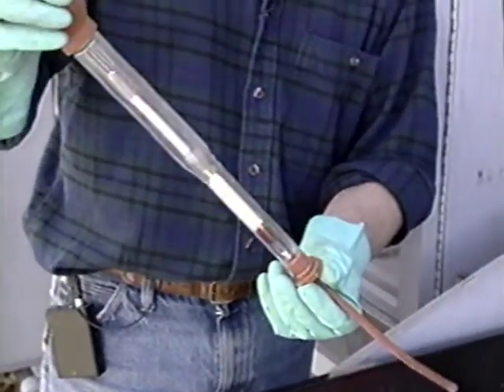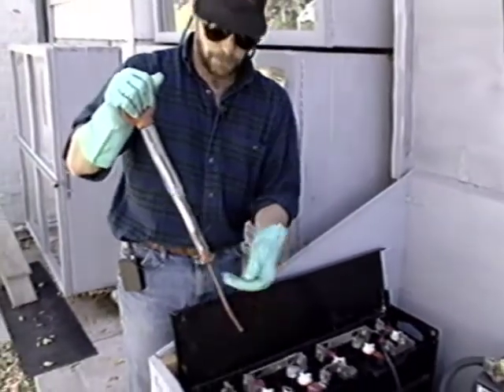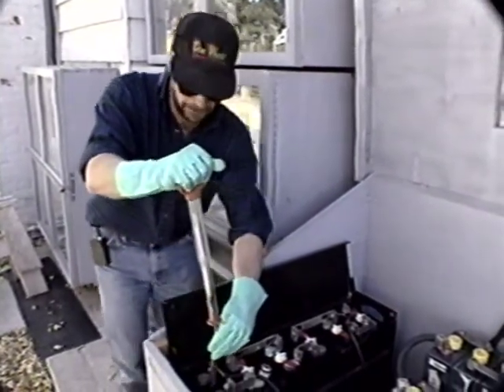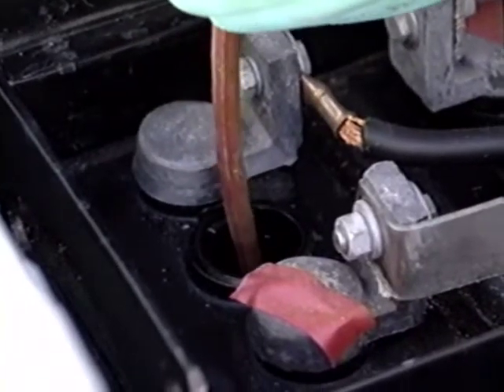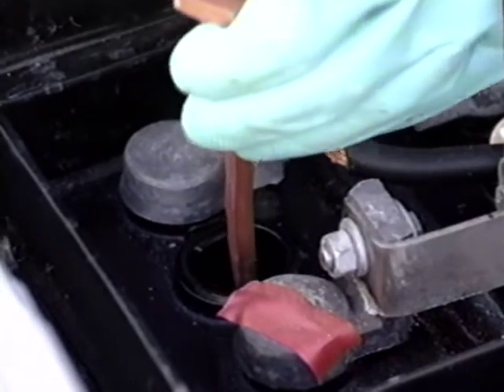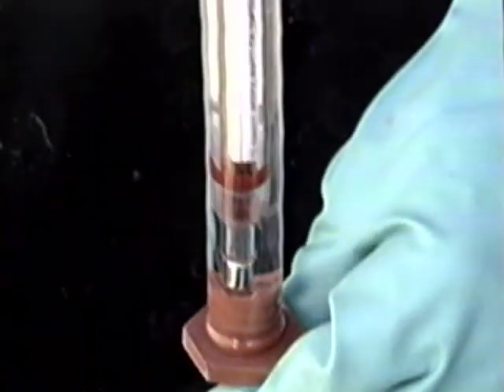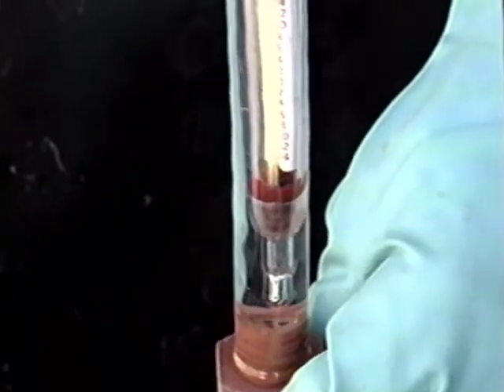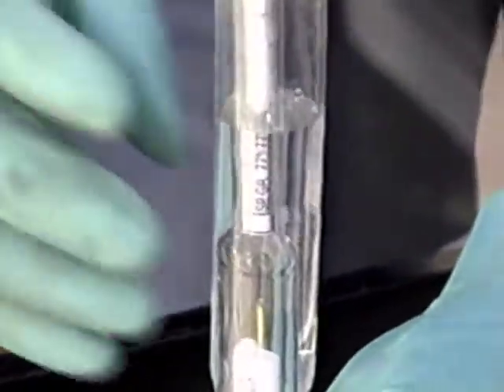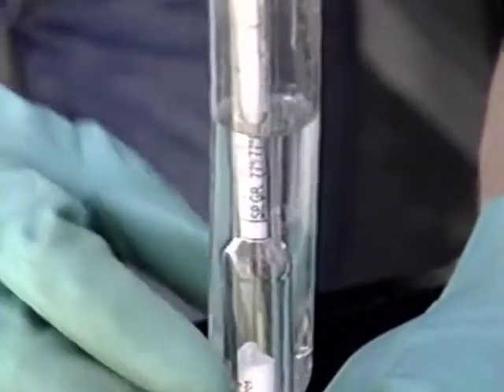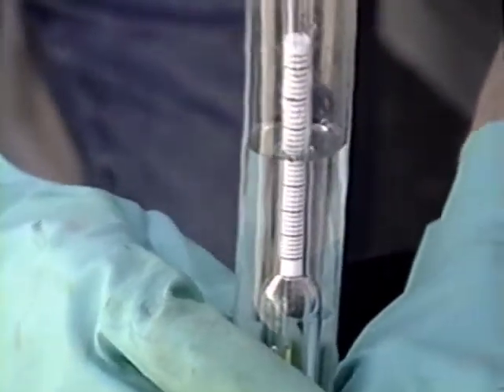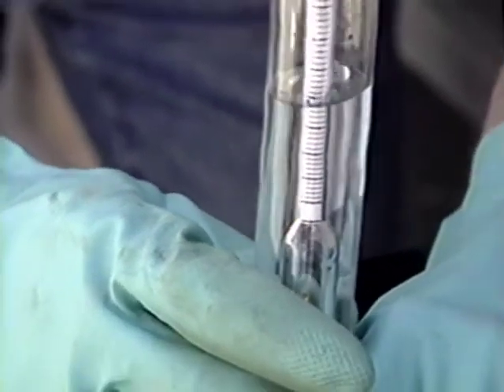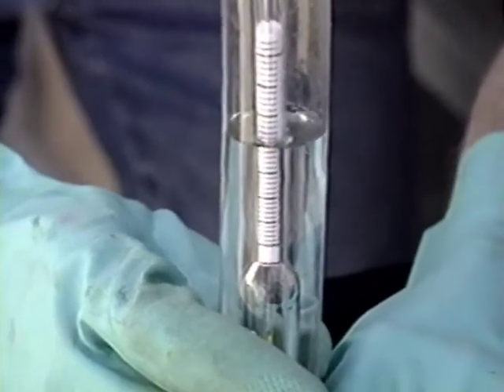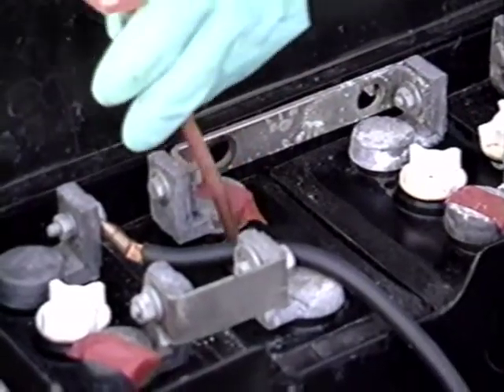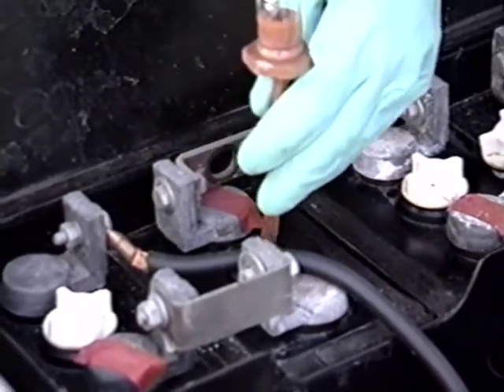It's important to remember to push the ball in before putting it down in here so you don't get any bubbling of this sulfuric acid. What you want to do is very carefully draw up the electrolyte, the fluid, the sulfuric acid solution up into the hydrometer. And then, without spilling any of it, you can read the reading and check the actual state of charge of the battery cell. This is the best and only accurate way to measure the state of charge of a battery cell. Using a hydrometer like this is the best way to check for a weak cell in a battery bank.